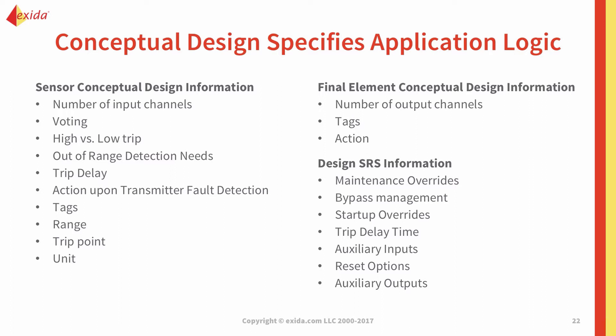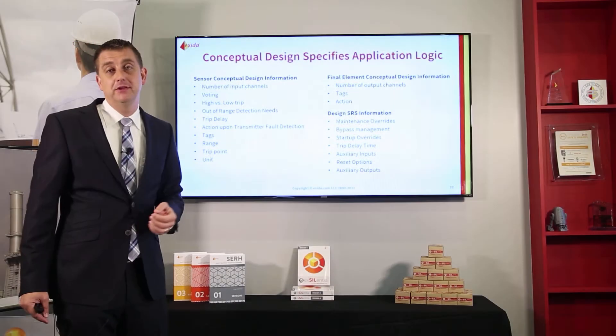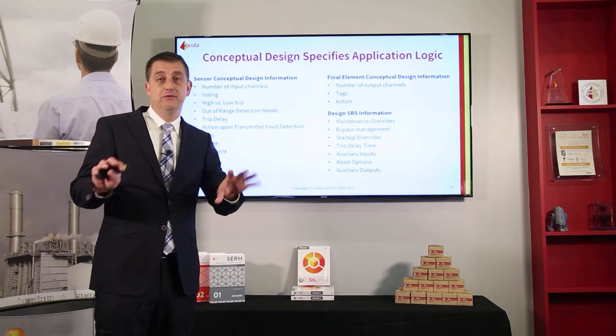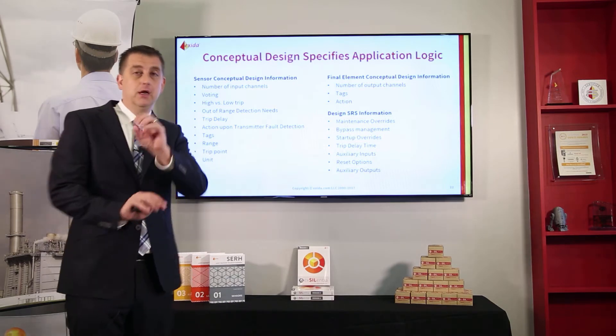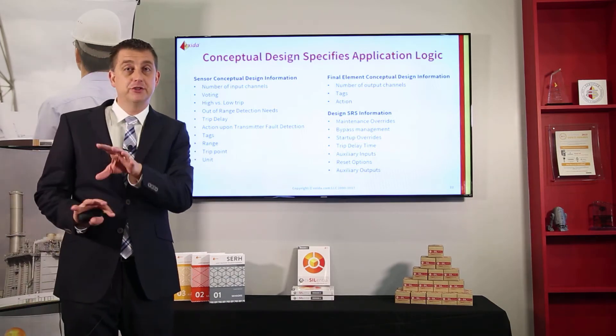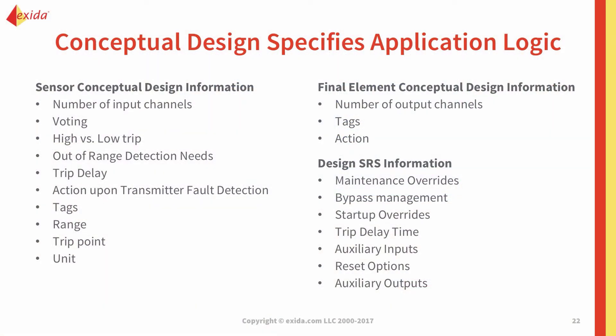On the final element side, we need to know how many outputs we're driving and what the tags are. We don't really look at voting for the outputs because that's a result of how the valves are piped in the field — two valves in series closing on trip is a one-out-of-two; two valves in parallel closing on trip is a two-out-of-two. In either case, the logic solver drives two valves. We also configure whether to energize or de-energize on trip, and based on that we may need to implement different logic.